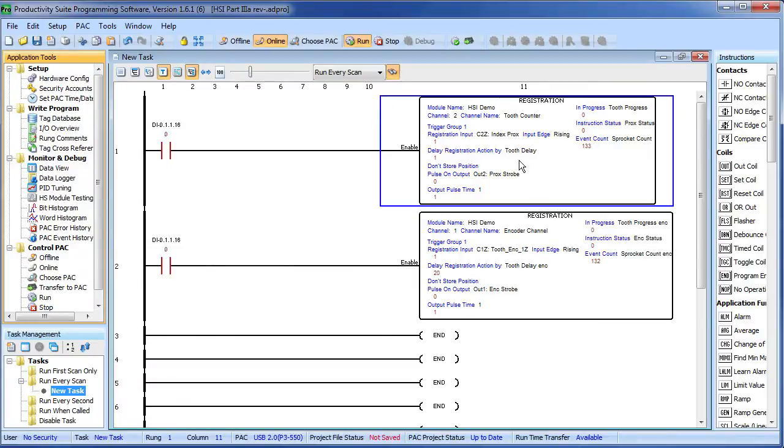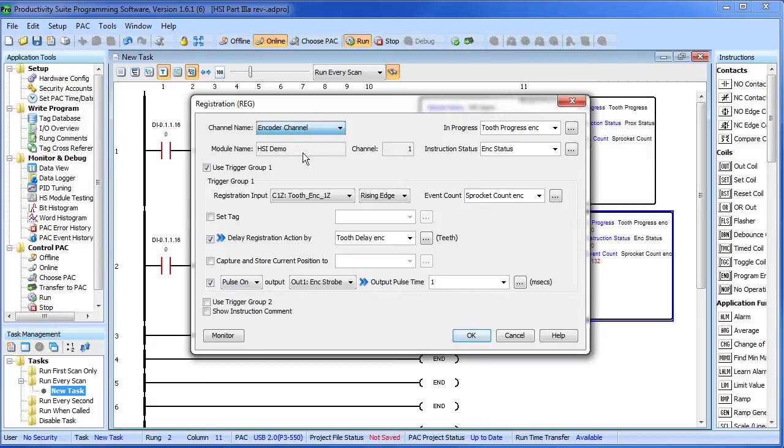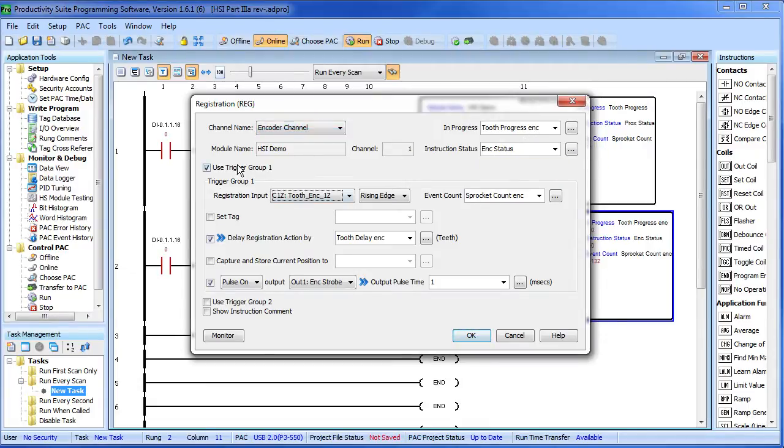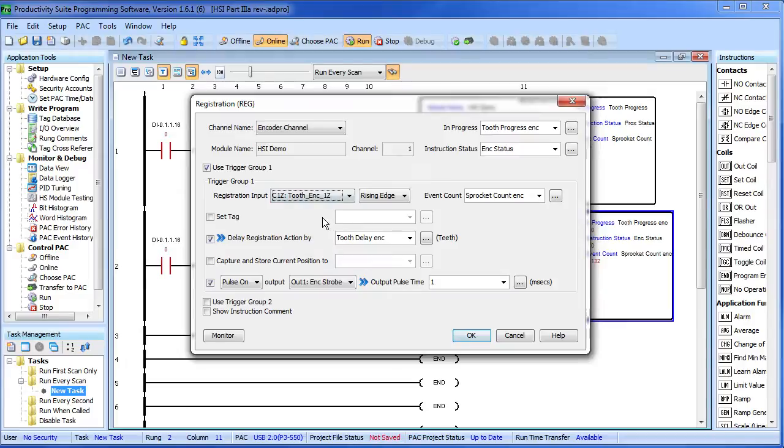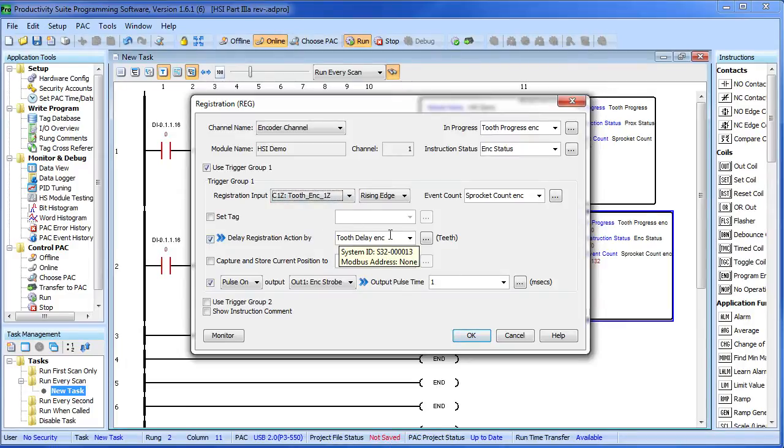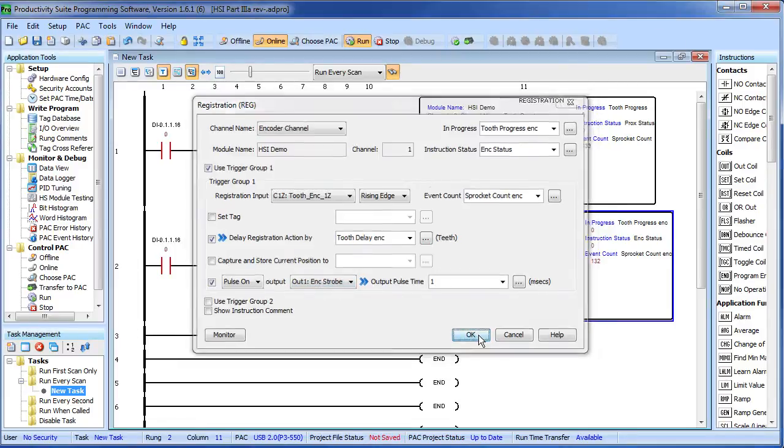So this is the registration instruction we had in the previous video for the PROX sensors. I simply copied that and created a second instruction. Instead of the PROX channel, we're using the encoder channel now, which is channel 1 on the HSI, and added an ENC for encoder to these status tags. Under trigger group 1, we want to trigger off of the encoder Z pulse now instead of the PROX like we had before. We're going to delay the registration action by some delay – I've created a new tag for that – and after that delay, we're going to pulse our strobe on output 1 instead of output 2 again for 1 millisecond.